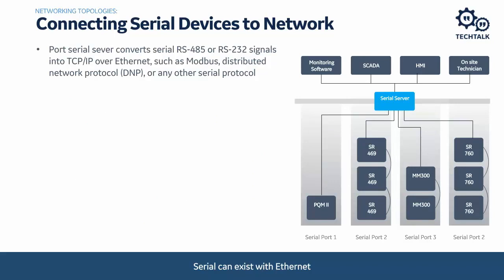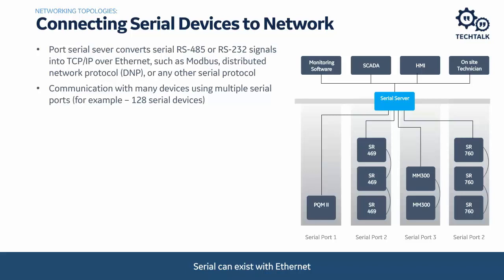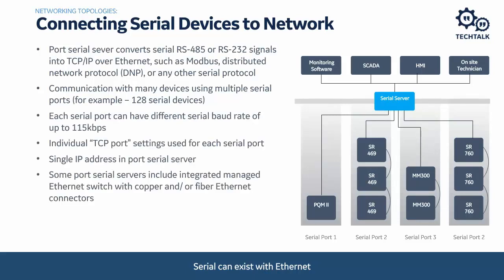We must also talk about interfacing legacy devices within an Ethernet network. If we do a brownfield project and create an Ethernet network while installing Ethernet devices, we will probably still have a number of serial devices available. Not a problem — we can have a hybrid network where we convert serial signals into an Ethernet signal using a serial server. These serial servers are available in various protocols, such as a DNP or 61850 converter, or a Modbus to DNP converter, converting serial DNP to Ethernet IP DNP or serial Modbus to Ethernet Modbus. Serial devices can exist within an Ethernet network.